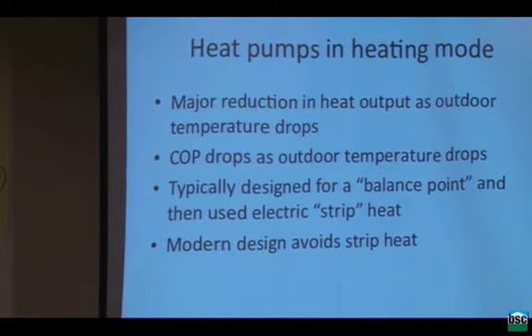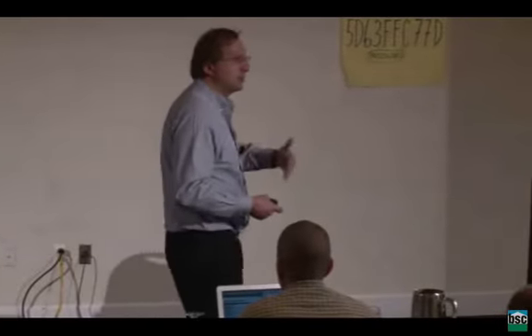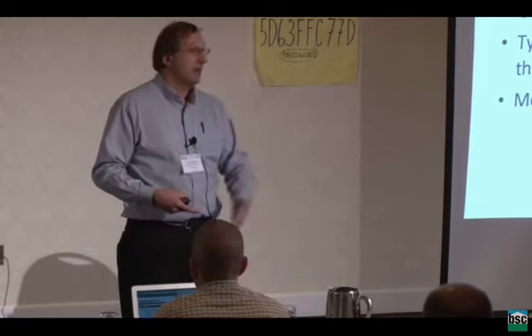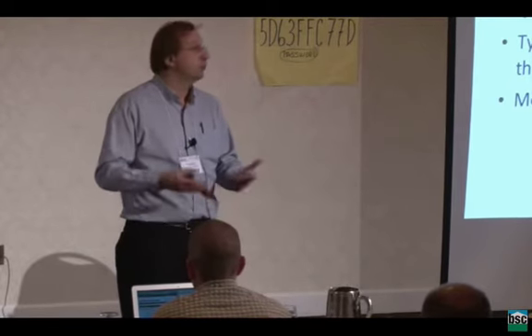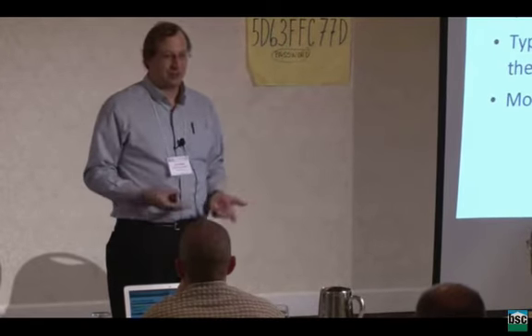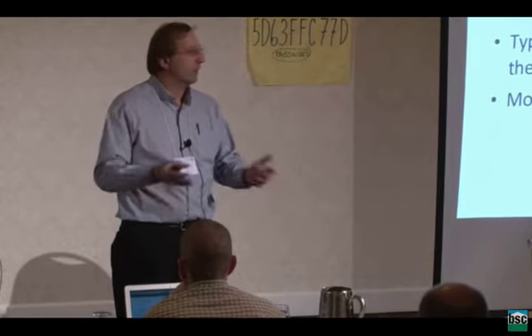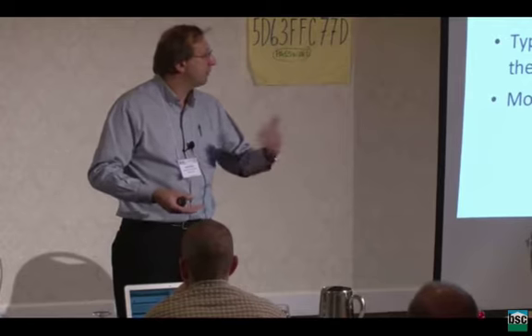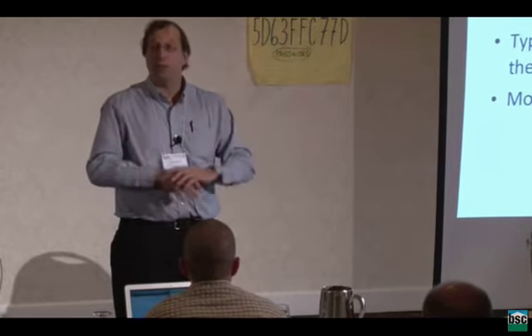Now what's interesting is that it doesn't just add to the heat pump output. No, it shuts the heat pump off and you go 100% electric. Part of the reason for that is that it's a single speed heat pump. If I add electric heat, I can have overcapacity. And so rather than doing that, they would just turn it all on. Now, since that time, they've gotten a lot smarter about it, and they will have staged strip heat, like 1, 2, or 3 stages. And you can often run the heat pump and 1 or 2 stages. And each stage would be a toaster or 2. I size things by toasters. They measure stuff by kilowatts. But your typical toaster is 1.5 kilowatts, and you can get strip heat in sizes of 1.5, 3, 4.5, 6, 9, things like that. So these are big electric strip heats.